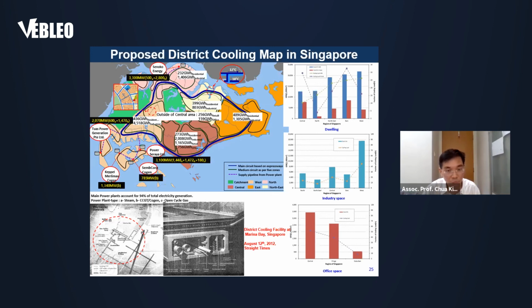So if we can imagine, typically the pipes of the district cooling that carry the chill water are all buried underground, right? And these pipes need to be heavily insulated by virtue of the fact that the chill water is running at 5 to 6 degrees and the outdoor temperature, for example, is about 30 degrees. So there's a big difference in temperature, and that's why you need your pipe to be heavily insulated. There's a lot of cost involved to insulate your pipe, right? To make it thick so that there's no heat loss from your chill water. That is previously, when it was operating at 5 to 6 degrees.